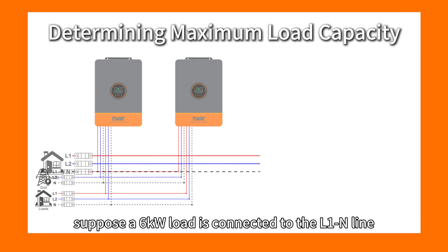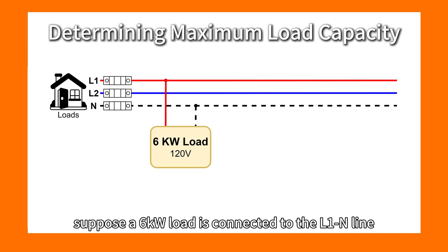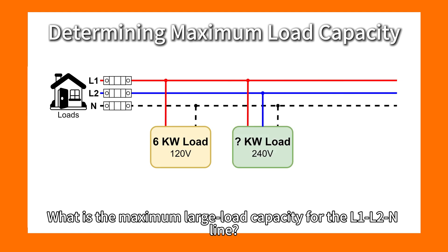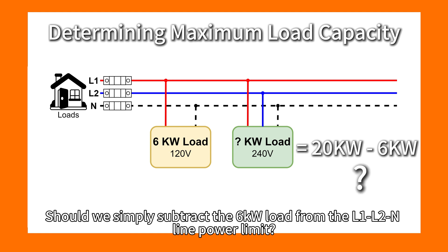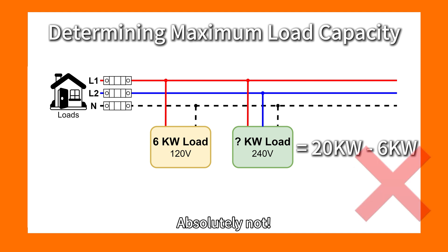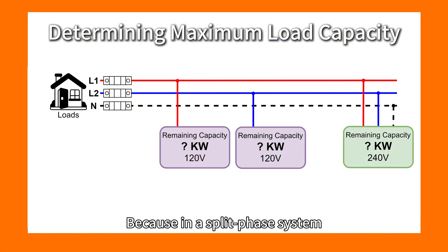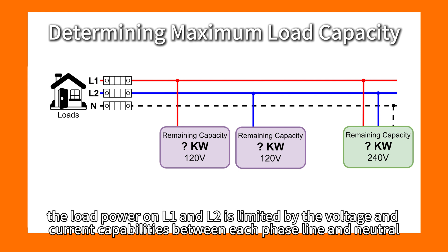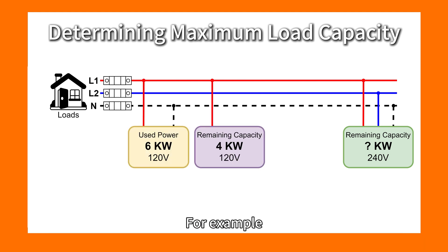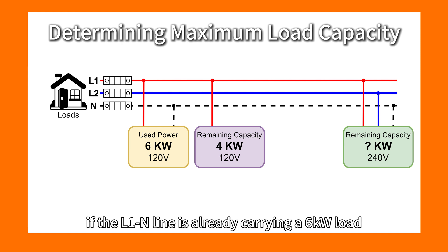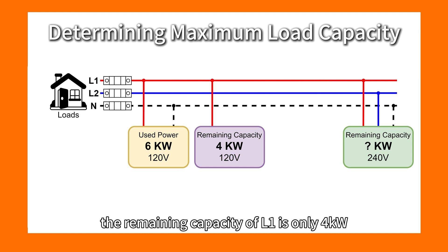Now suppose a 6kW load is connected to the L1-N line. What is the maximum load capacity for the L1-L2 line? Should we simply subtract the 6kW load from the L1-L2 line power limit? Absolutely not. Because in the split-phase system, the load power on L1 and L2 is limited by the voltage and current capabilities between each phase line and the neutral. If the L1-N line is already carrying a 6kW load, the remaining capacity of L1 is only 4kW.